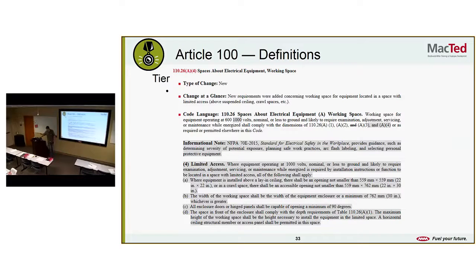We have a new definition in spaces about electrical equipment, working space. New requirements were added concerning working space for equipment located in a space with limited access, so above ceilings, crawl spaces, etc. This is probably something some of the installers need to read, and the engineers that spec out where things are put. Working space for equipment operating at 600, oh, they added, so 600, now 1,000 volts nominal or less to ground and likely to require examination, adjustment, servicing, or maintenance while energized, shall comply with the dimensions in 110.26(A) and some others there.